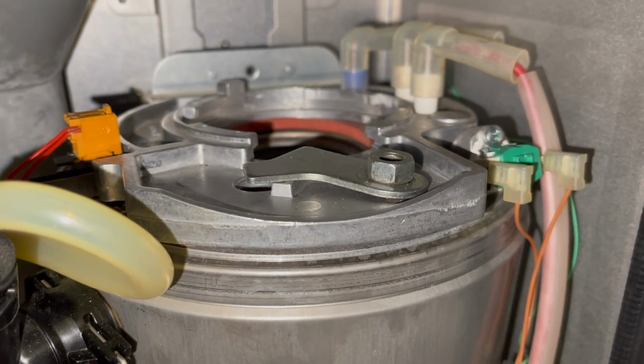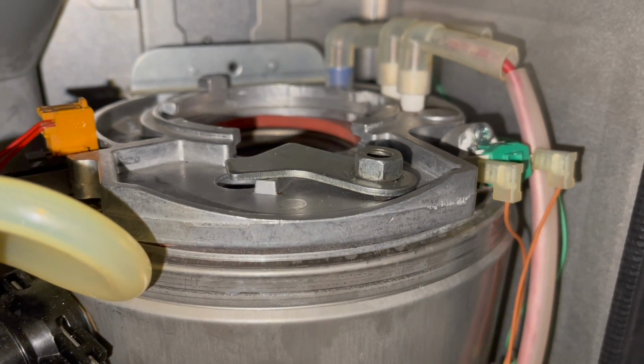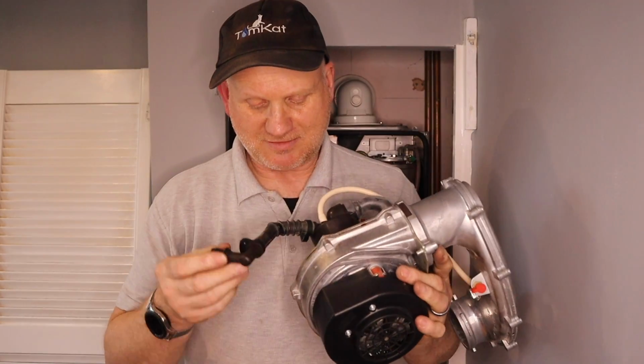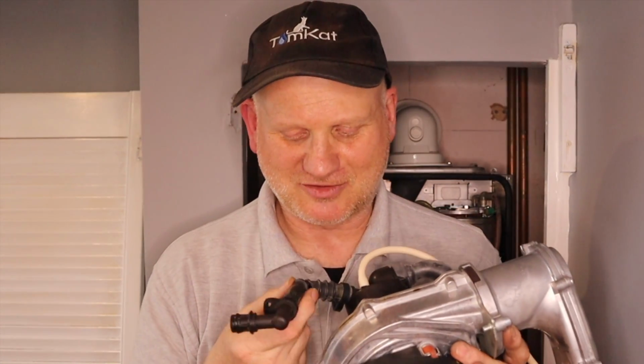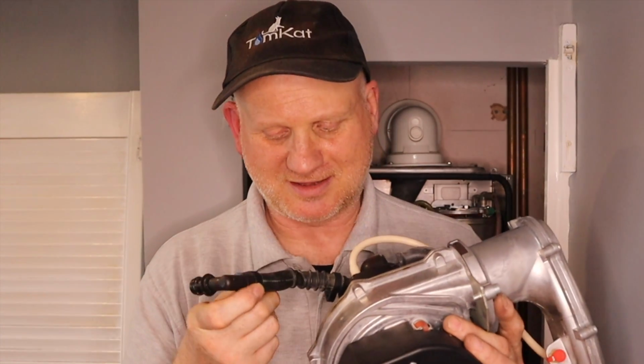Now we should be able to get the fan back in the gas valve. Another thing I've just noticed, see that big split where the gas tube comes in? This is another fault what happens to them, as long, and the bearing what's in there. So again, it's a good job I've got some of these at the centre and I can just go and replace this tube. But this is what you're up against when boilers are not serviced on a regular basis.